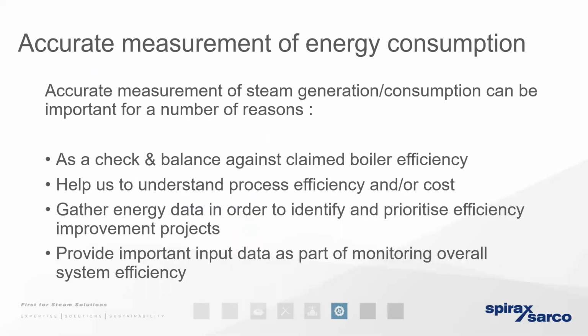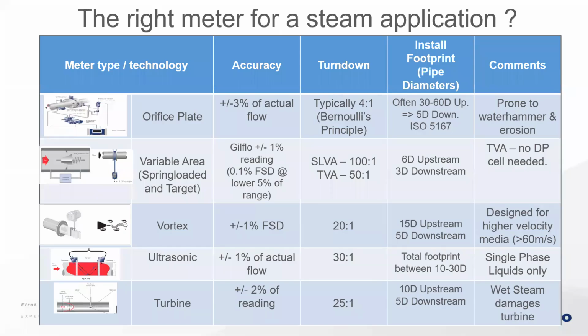Now, we also know that metering the steam, both in the boiler house and at the process, is critically important. It can help us understand the overall efficiency, not just in the boiler house, but also at the process as well. The key thing is understanding that we need to select the correct type of steam meter to match the process. As with steam traps, there's no such thing as a universal steam meter. They all operate in different ways.